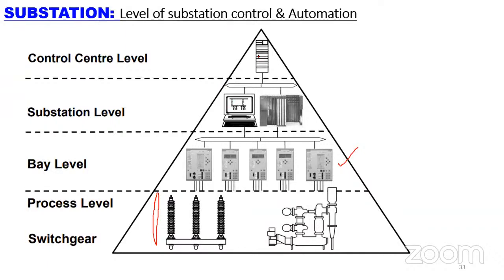There are also control systems at a remote end. A group of substations, maybe more than 100, let's say 50 substations, is monitored from the control center. These regional control centers have multiple PCs and multiple screens. It helps to monitor the various substations, and to do energy monitoring as well as monitor the reliability of the whole network. So these are the different levels of substation automation: switchgear level, then bay level, then substation level, and control center level.